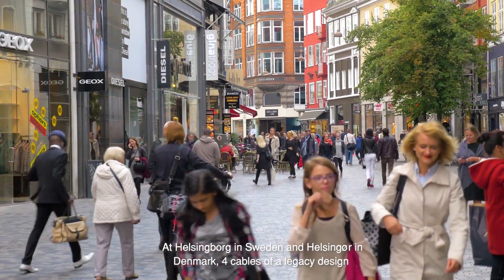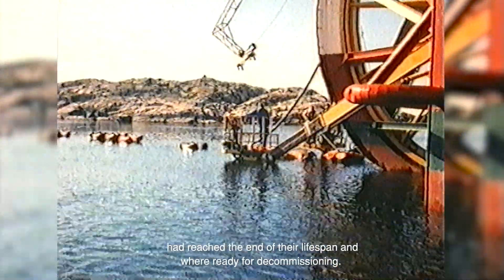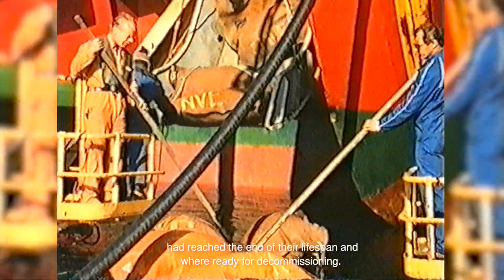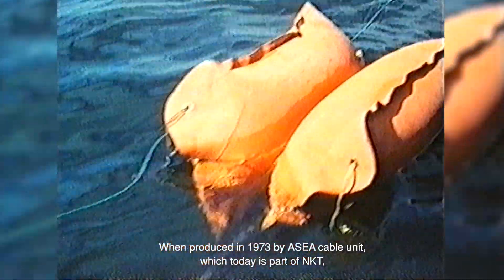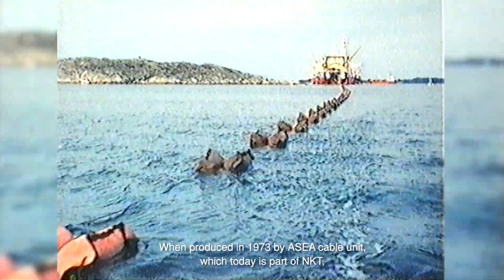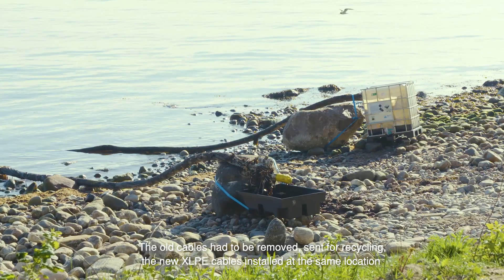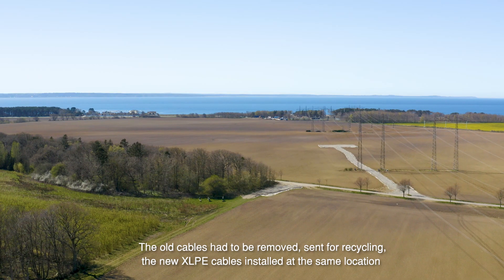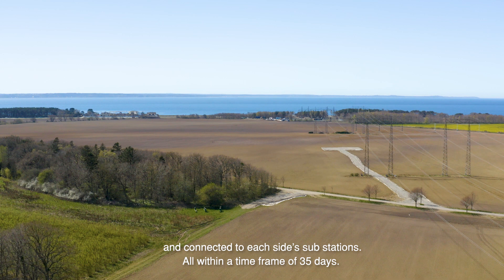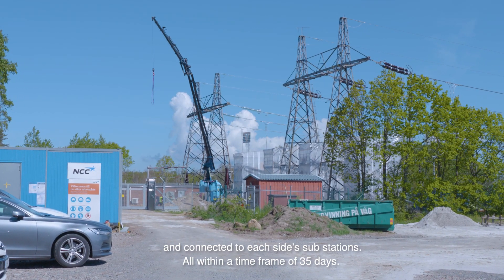At Helsingborg in Sweden and Helsingør in Denmark, four cables of a legacy design had reached the end of their lifespan and were ready for decommissioning. When produced in 1973 by ASEA cable unit, which today is part of NKT, they were at that time the world's first offshore LPOF cables at this voltage level. The old cables had to be removed, sent for recycling, and new XLPE cables installed at the same location and connected to each side's substations — all within a timeframe of 35 days.